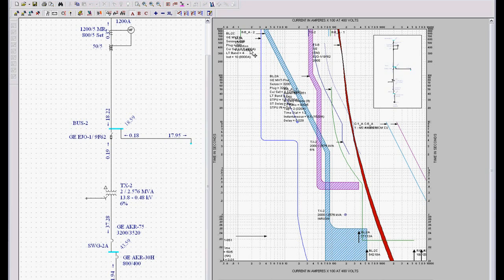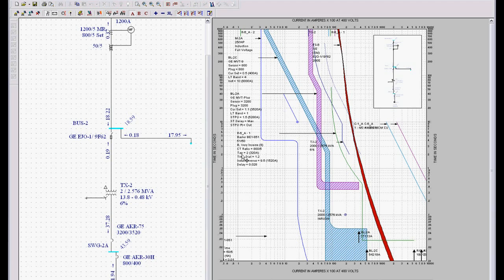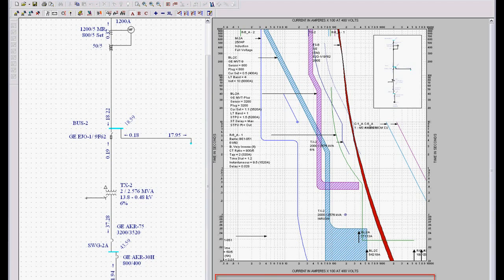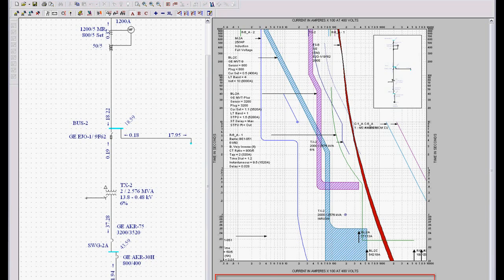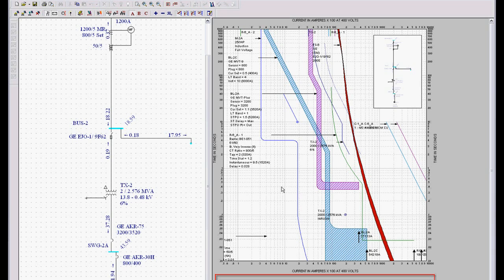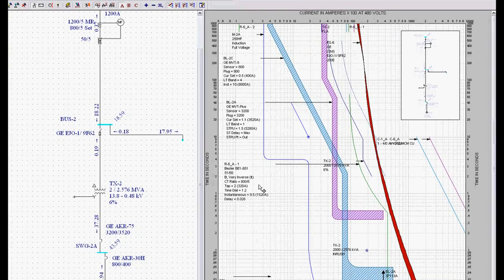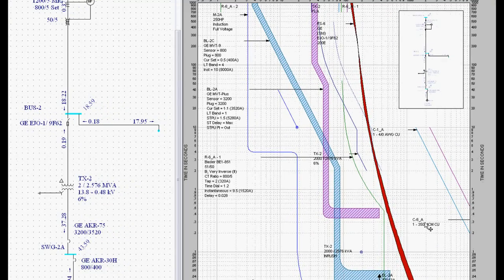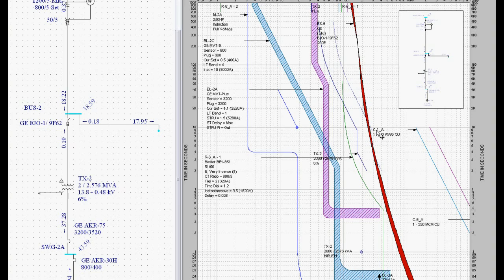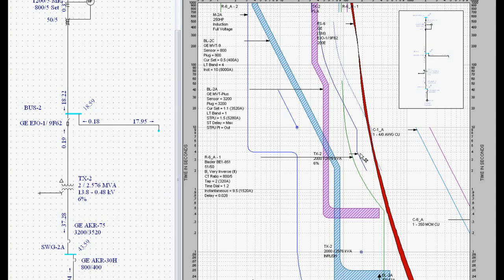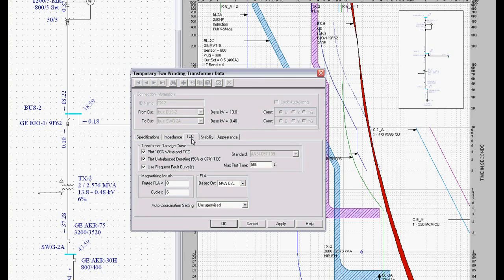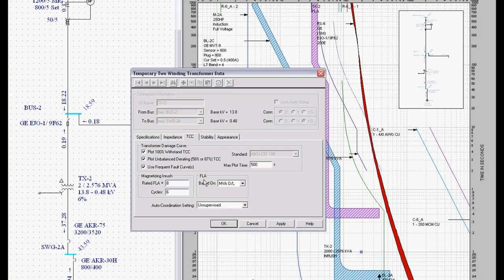Now over on the right hand side of the system are my time current curves. Now I'm going to close this title block. We're going to get rid of that so you can see this information a little bit larger. Now we do that by clicking this little button. So now you can see that a little bit better. Now the key things to note as we're looking through this, remember when we were in the time current curve tab of this transformer? If I click on this you'll see the time current curve tab where we plot the 100% withstand, the unbalanced derating, and so on.